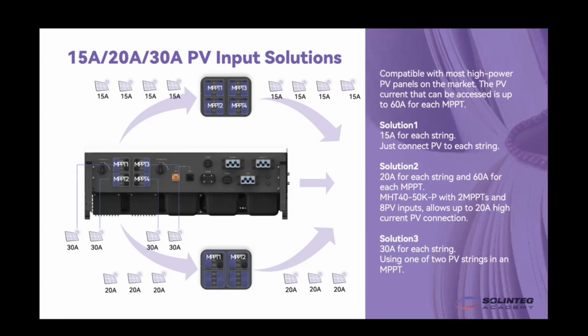And what if we want to use some high power PV strings, where the current has reached, for example, 17 ampere? In this case, we can choose to use the Plus version of this inverter, which has 2 MPPTs and 4 PV inputs in 1 MPPT. We can just use 3 PV inputs, and in this case each PV input can accept a current of 20 ampere. That is why we can connect with some higher current PV panels.